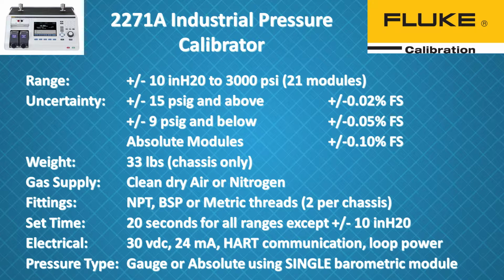The weight of the unit is about 33 pounds, so it's not light, but it would be pretty easy to put this on a cart with a gas bottle, for instance, for doing portable calibrations. It does require clean, dry air or nitrogen. It does not have an internal pump like some of the Additel product that we looked at before, but there are some small-size gas cylinders you can get and mount those on carts to wheel around your facility. The fittings are NPT, BSP, or metric threads. I believe metric threads are available. At the show, the unit that was on demonstration there had metric threads.